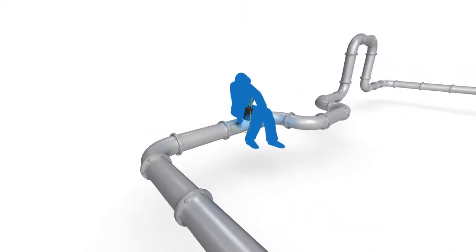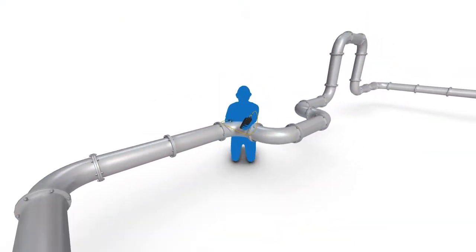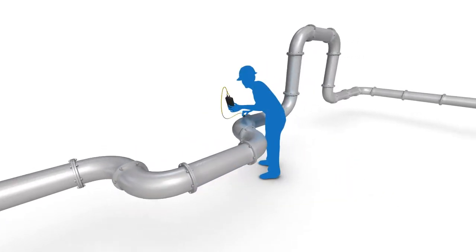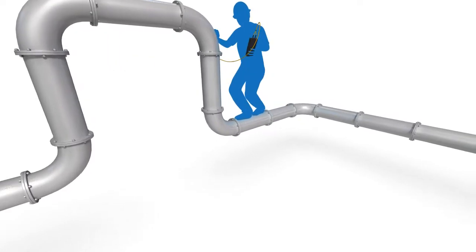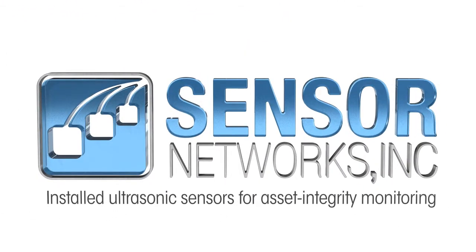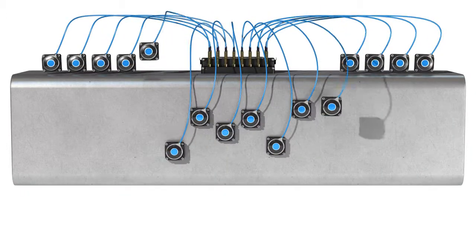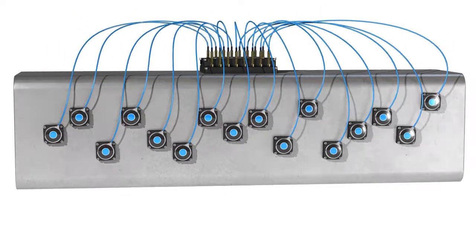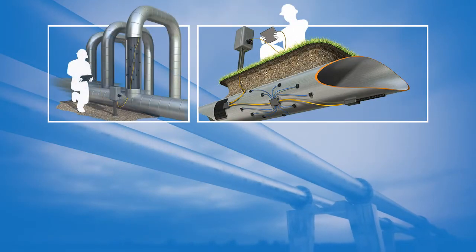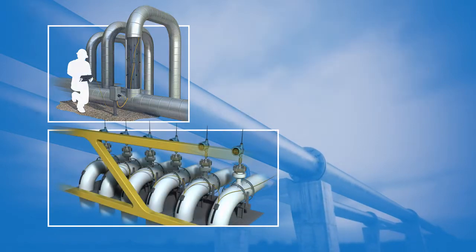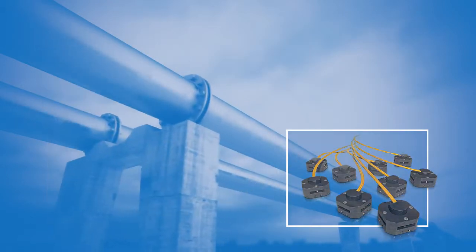Until now, inspecting for corrosion, erosion, and cracking was a slow manual process, fraught with safety risks, high cost, and poor data integrity. But Sensor Networks is changing that, with a new breed of automated corrosion monitoring technology based on installed ultrasonic sensors — a technology capable of accurately measuring remaining wall thickness and calculating corrosion and erosion rates.